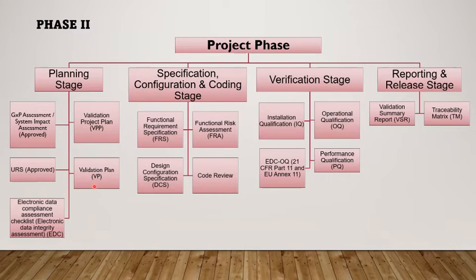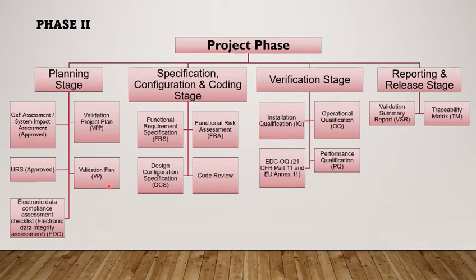Next is the validation plan, which is a very important deliverable in which you include all the validation strategies. The validation plan describes the purpose, scope, responsibilities, system details, implementation methodology, and data migration if applicable. It also defines what deliverables are required as per different GAMP categories, the acceptance criteria for IQ, OQ and PQ, and also defines the strategies for leveraging test scripts from vendor documents, which can be very helpful to avoid duplication of testing.